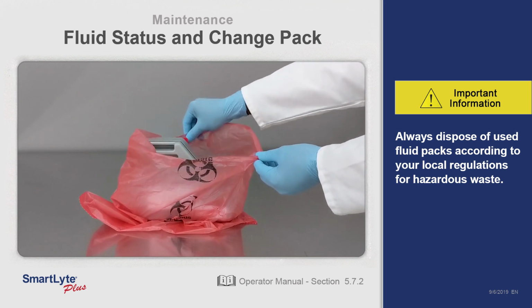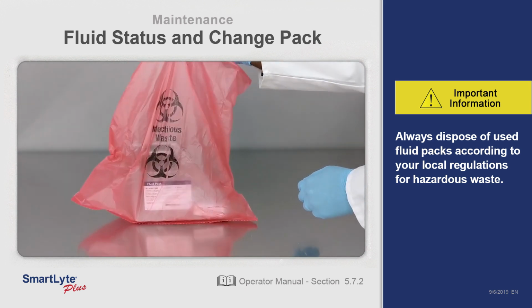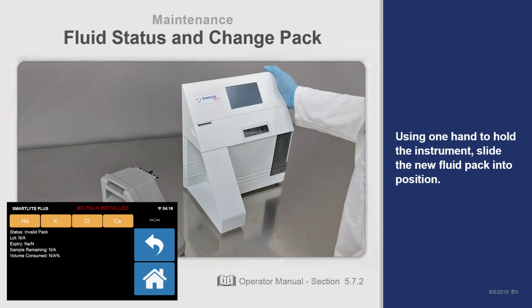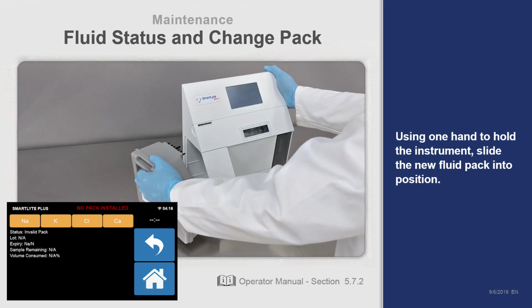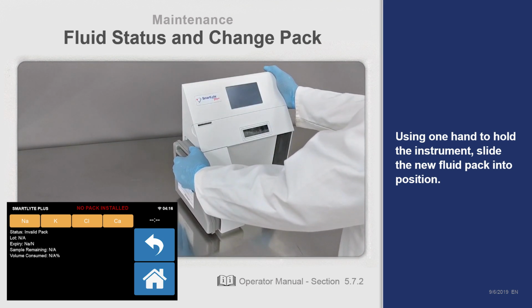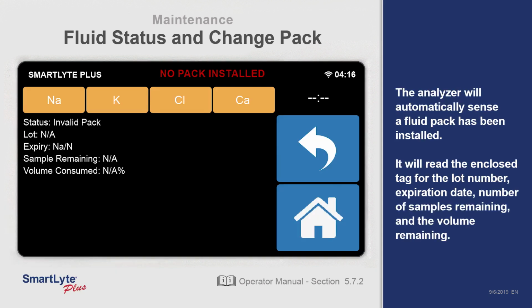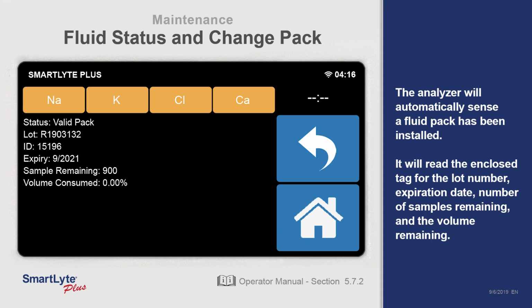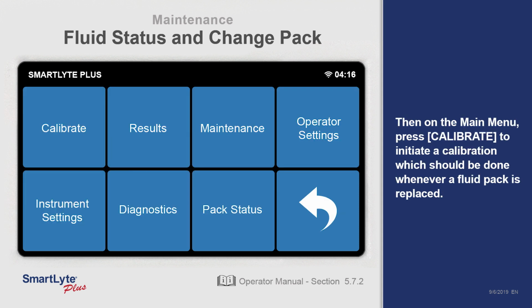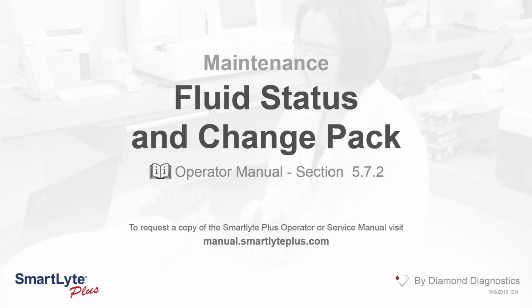Always dispose of used fluid packs according to your local regulations for hazardous waste. Using one hand to hold the instrument, slide the new fluid pack into position. The analyzer will automatically sense a fluid pack has been installed. It will read the enclosed tag for the lot number, expiration date, number of samples remaining, and the volume remaining. Then, on the main menu, press Calibrate to initiate a calibration, which should be done whenever a fluid pack is replaced.